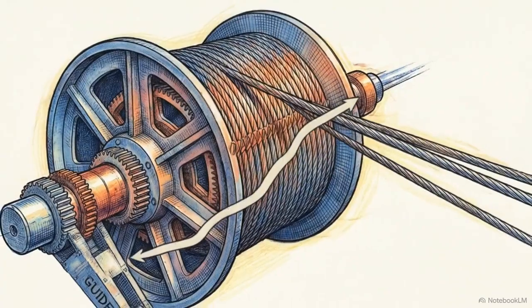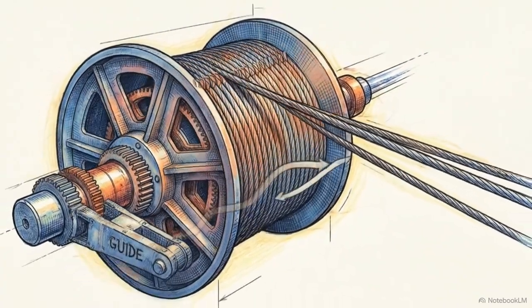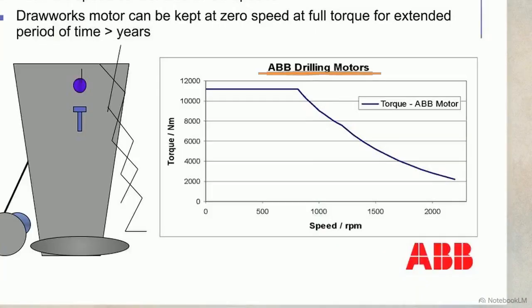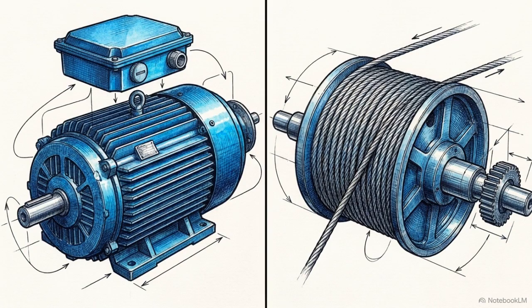The ultimate performance test for any offshore drive system is the drawworks, which must suspend hundreds of thousands of pounds of drill pipe. This chart shows the torque speed curve for an ABB drilling motor. Modern AC VSDs deliver 100% of their rated holding torque at exactly 0 RPM, preventing the load from creeping during stationary operations. AC systems moved the industry forward by removing catastrophic maintenance failure points while improving low-speed torque control.